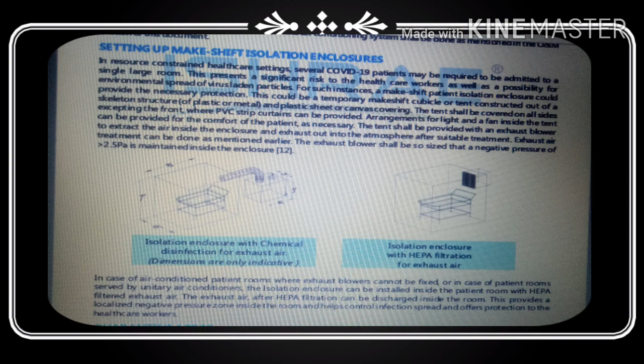So chemical disinfection of the exhaust air from a COVID-19 patient room can be done by bubbling the exhaust air through a diffused air aerator tank holding 1% sodium hypochlorite solution. The concentration shall be checked on a regular basis and dosing undertaken as needed. The aeration tank shall be placed in an unpopulated outdoor area and not inside an enclosed space.